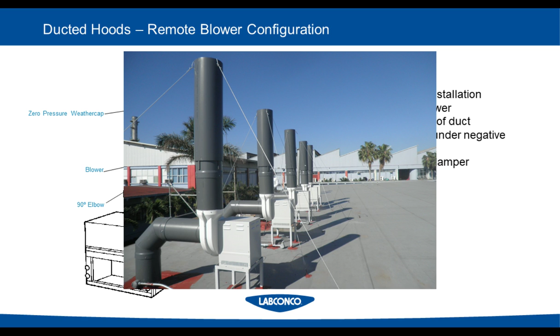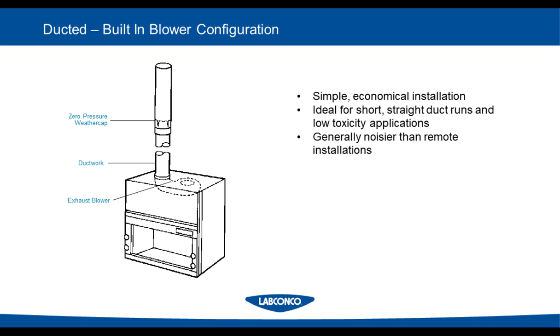This is because it puts the blower right on top of the fume hood instead of on top of the building, where there are a lot of bends and connections that need to be made between the two. They are generally noisier than remote blower installations. As I've said, this puts the blower right at the outlet of the fume hood instead of really far away with a remote blower. That means you hear the blower a lot better in this type of situation.